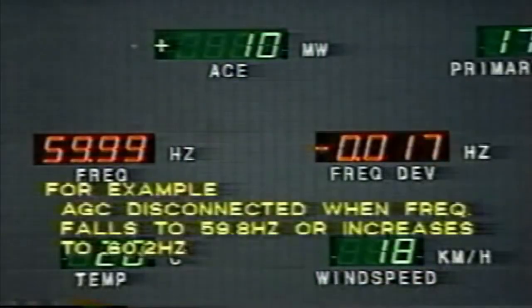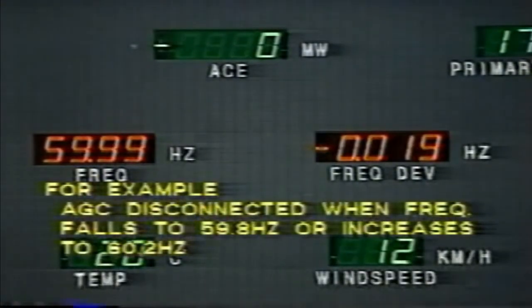In practice, the AGC is disconnected automatically when frequency falls to 59.8 hertz or increases to 60.2 hertz. In this situation, the operator obviously has his hands full, and perhaps some hours may pass before the system can be restored to normal. In order to prevent this disastrous and dramatic turn of events, the system operator must endeavor to keep the system fully intact as far as possible.